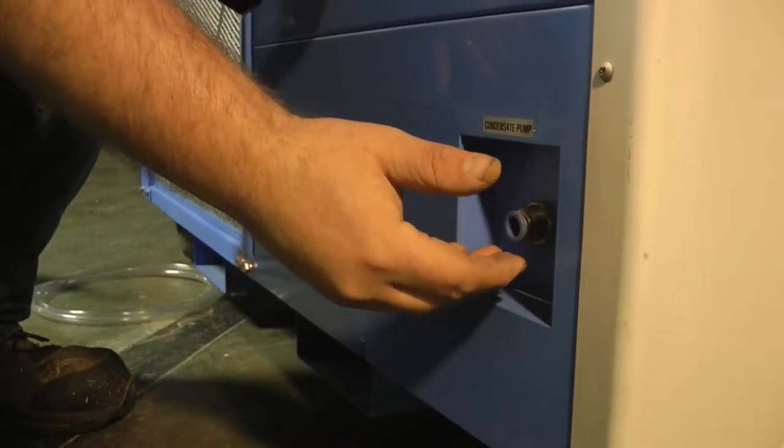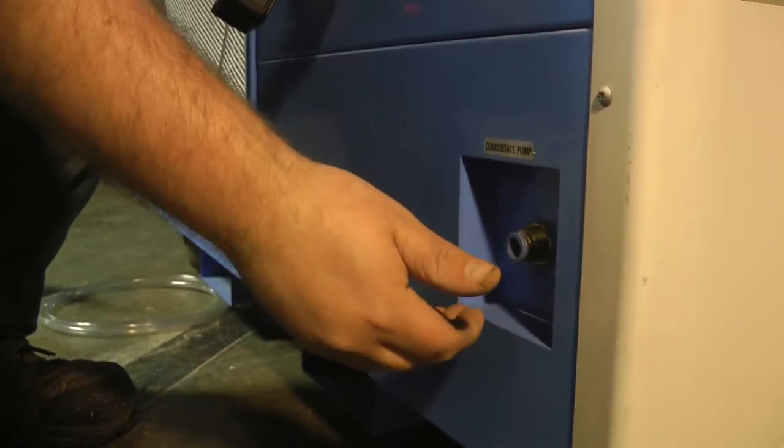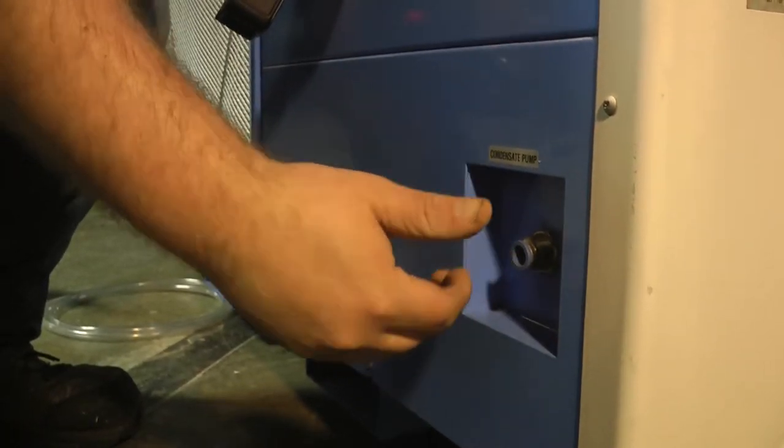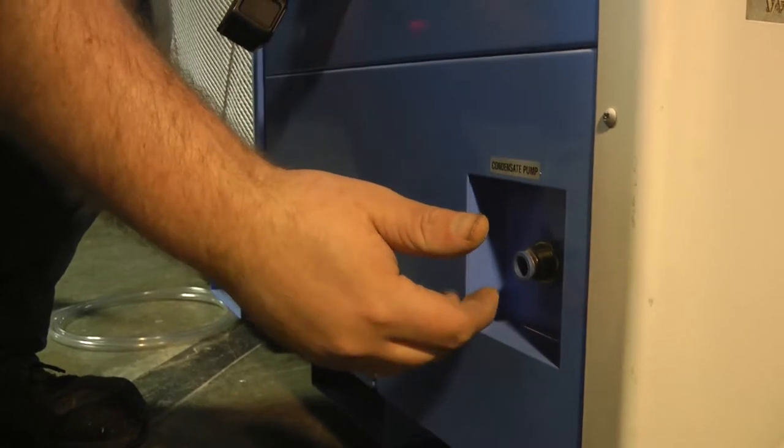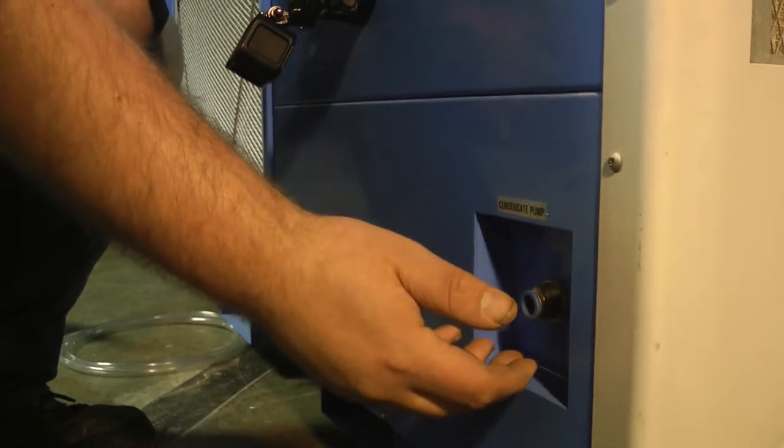So what tends to happen sometimes is it'll start leaking out of this fitting. I'm going to demonstrate how to go about correcting this and we're going to reroute your condensate line directly to the pump and remove this fitting altogether so we don't have any leaking problems.